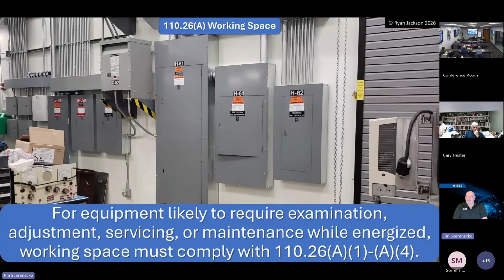Now, this is always the big argument too: equipment likely to require examination, adjustment, servicing, or maintenance while energized needs working space. What doesn't require energization to troubleshoot? I mean, you can't hardly do anything unless it's energized. You don't even know how it works or see what's going on. So it always comes up like, hey, I'm never going to work on this while it's energized. Well, you're never going to figure out what's wrong with it unless you do.